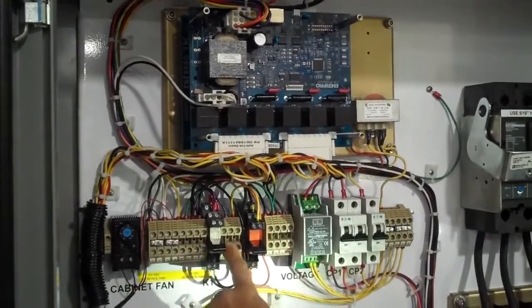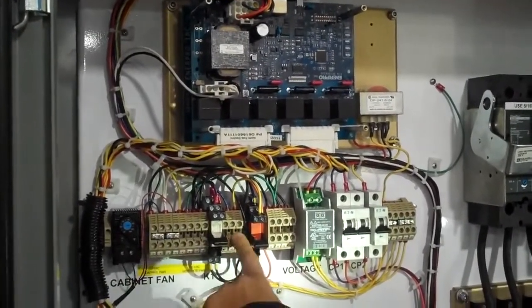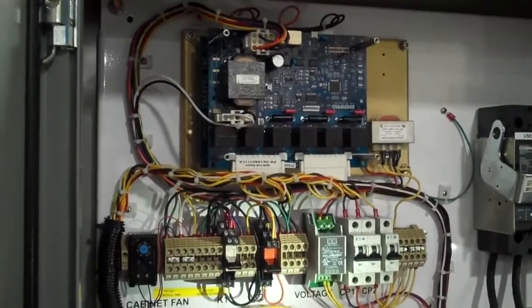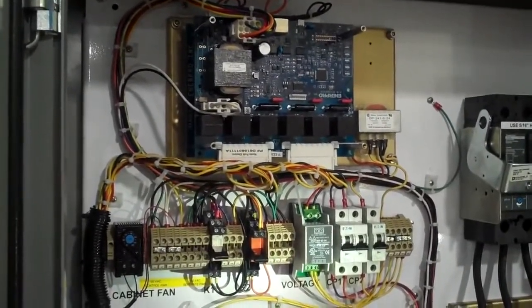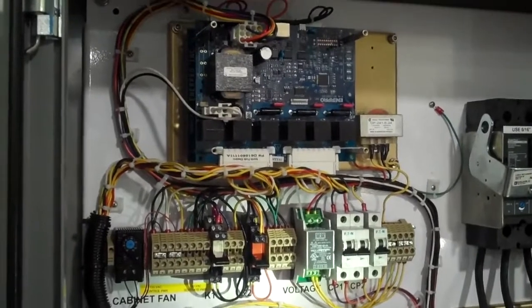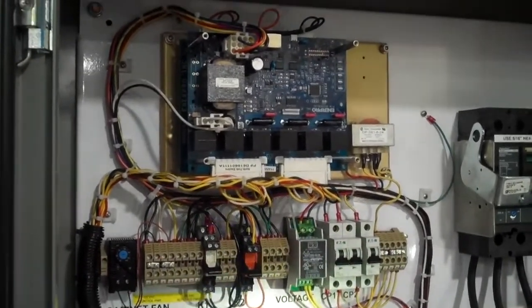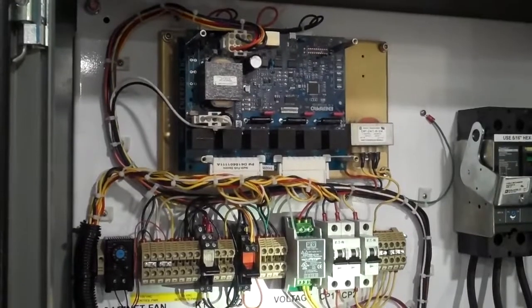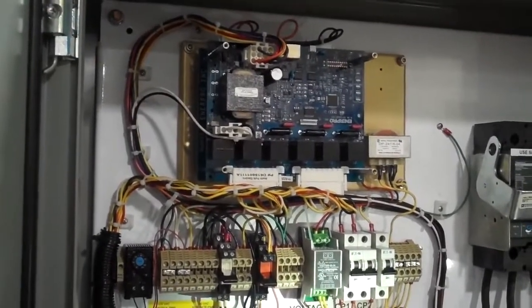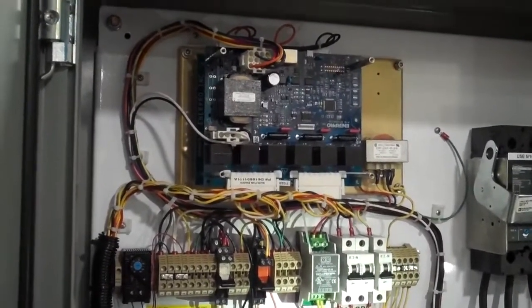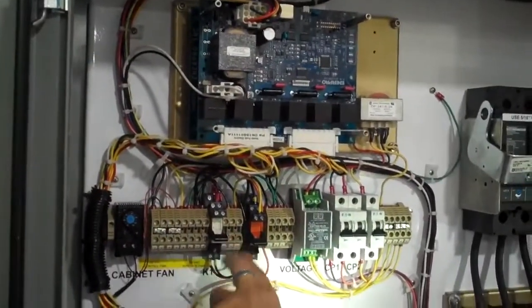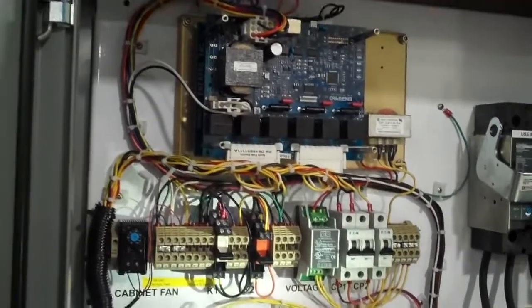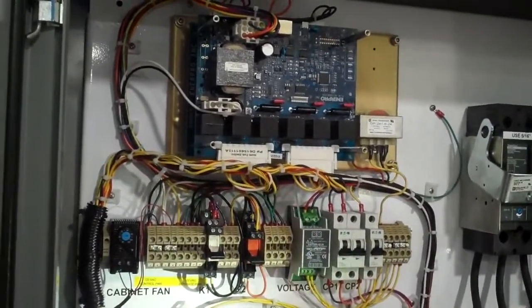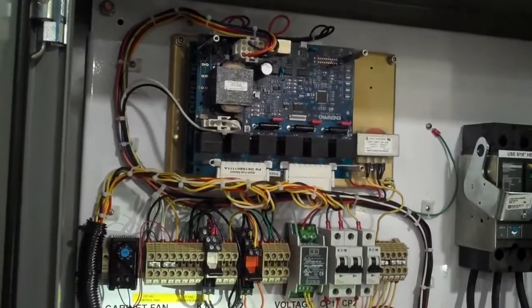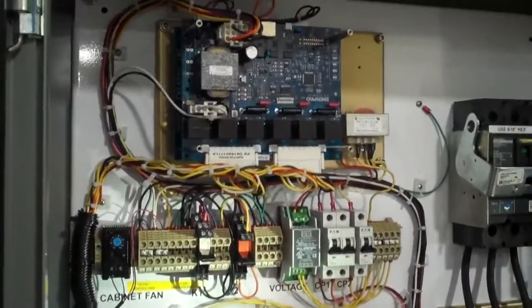Then moving along, between 9 and 10 we have what we define as an emergency stop. This normally has to be jumpered, but when we show a test, we'll have a switch. But the vision here is for the customer to provide a normally closed contact that will open when there's an emergency. So it can be an emergency button or an emergency signal going into 9 and 10.